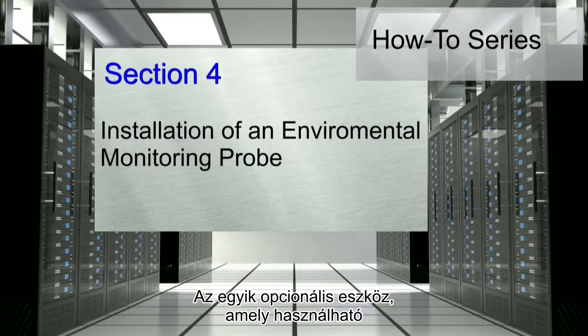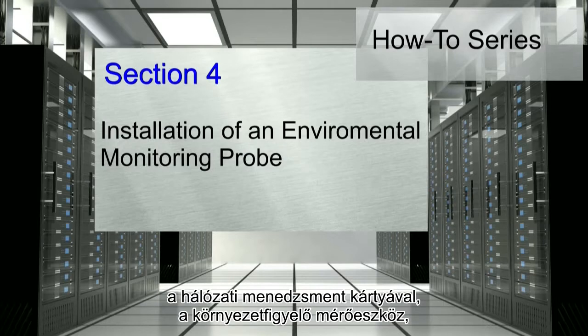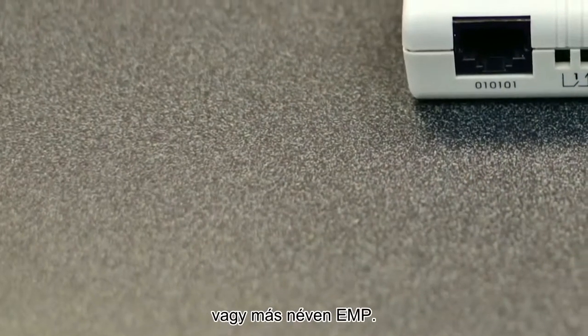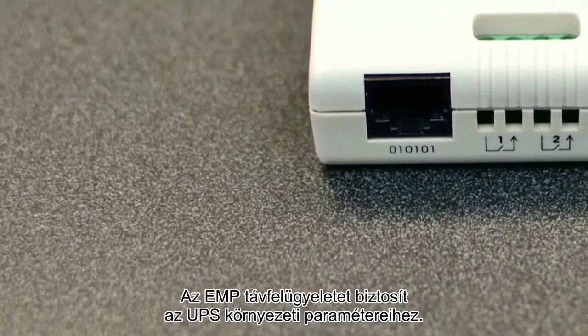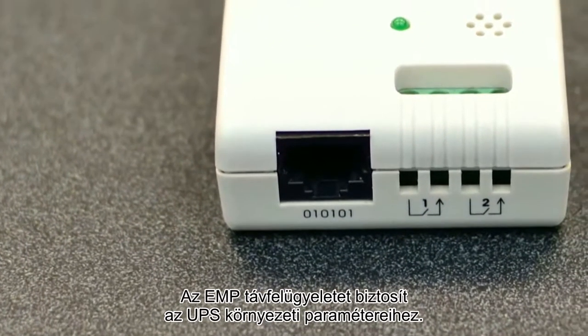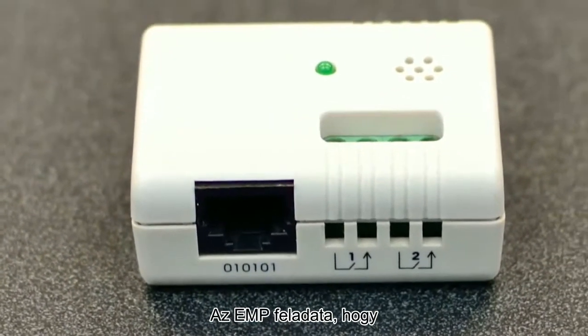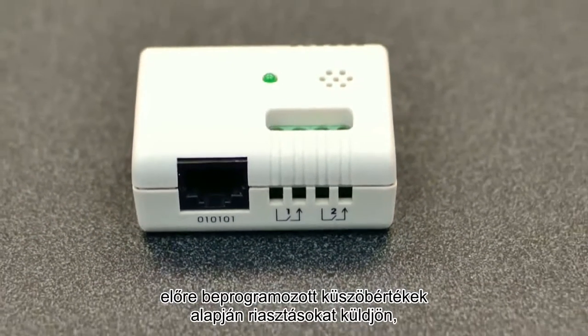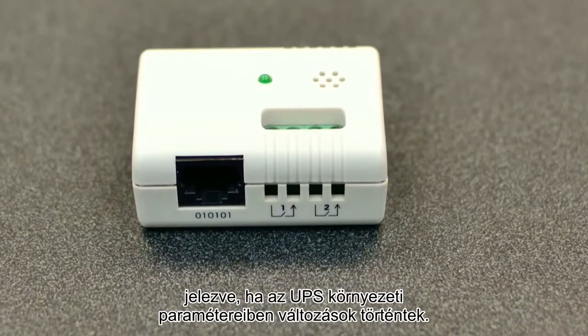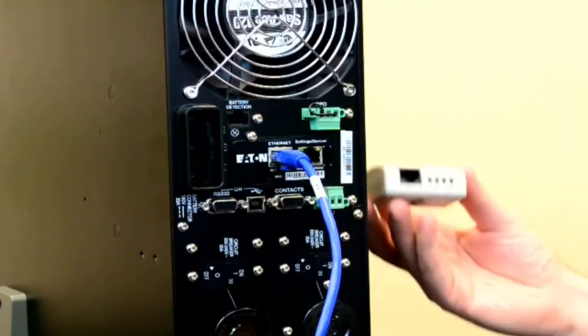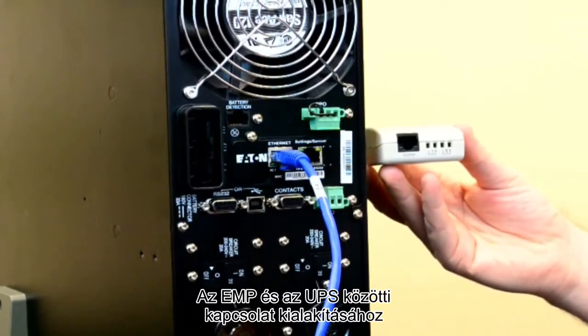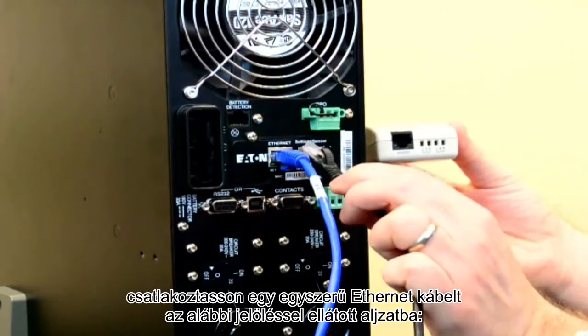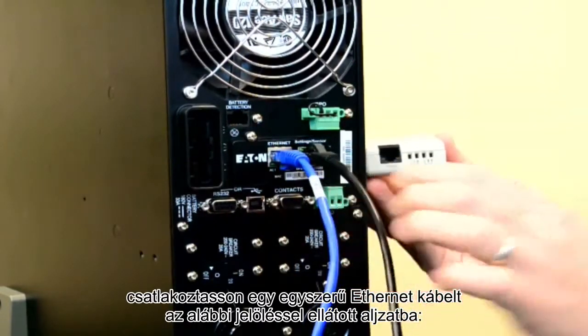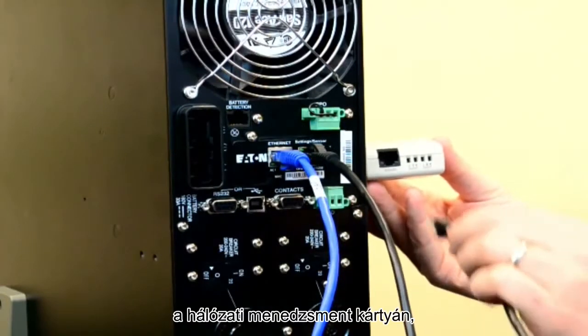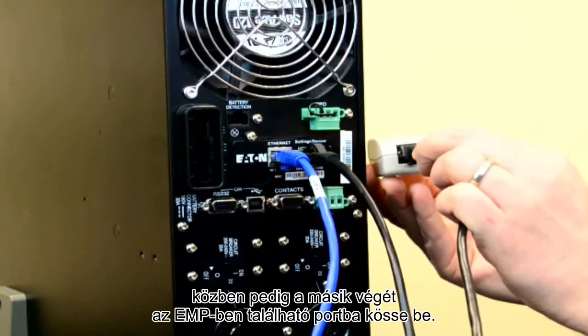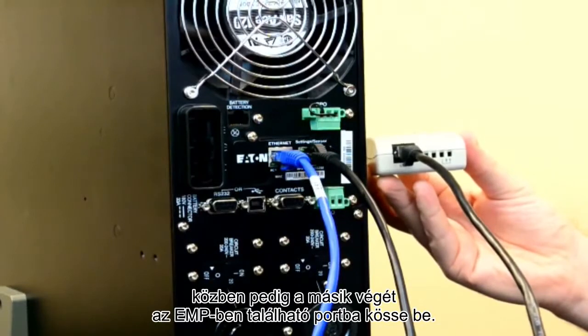An optional device which can be used with the Network Management card is the Environmental Monitoring Probe, also known as the EMP. The EMP provides remote monitoring for the UPS environment. The function of the EMP is to send alerts based on pre-programmed thresholds in order to indicate changes within the UPS environment. In order to establish a connection between the EMP and UPS, connect a standard Ethernet cable into the slot identified as setting/sensor on the Network Management card while connecting the opposite end to the port in the EMP.